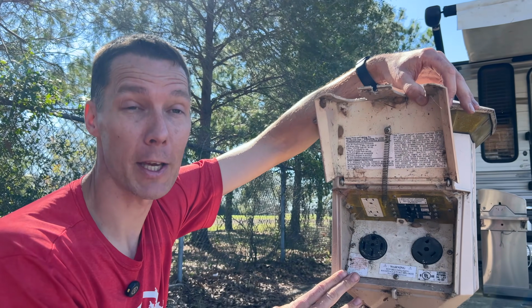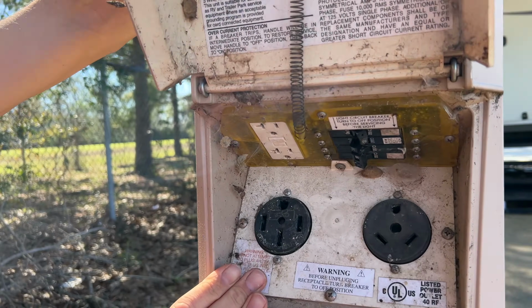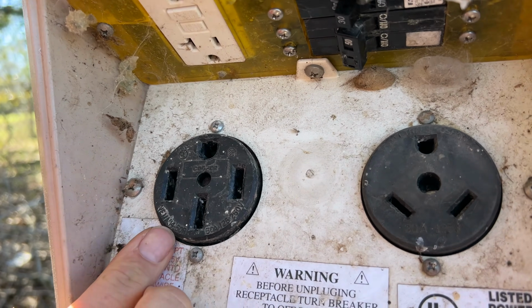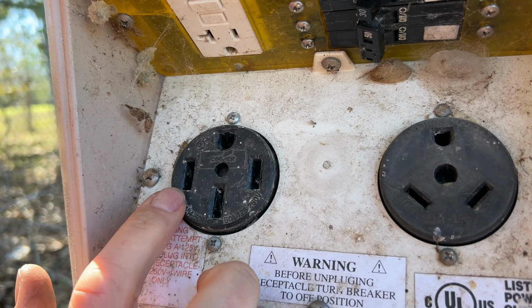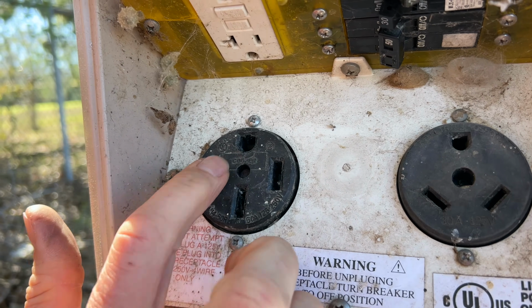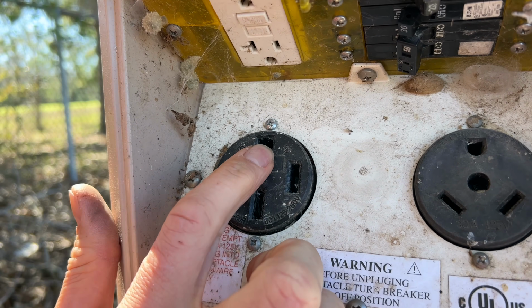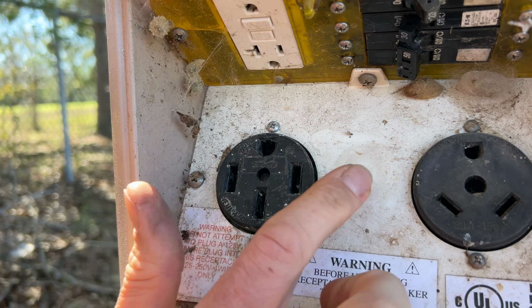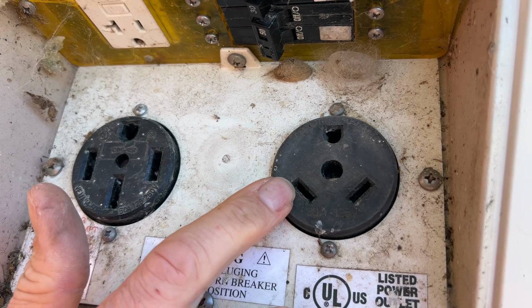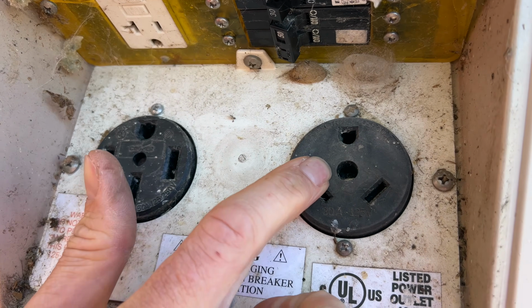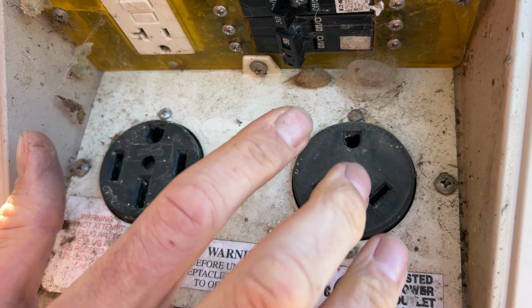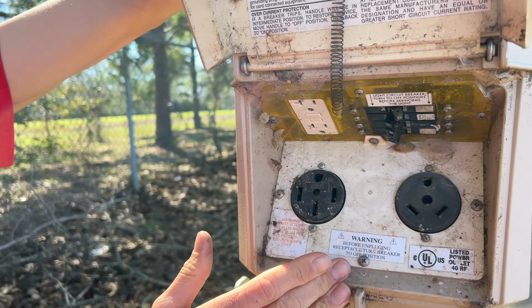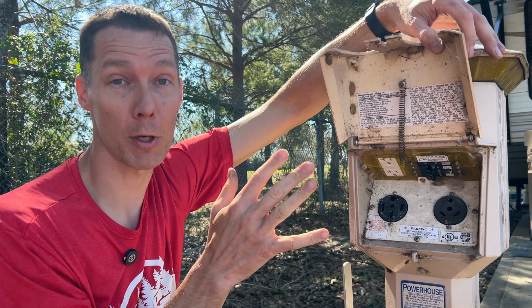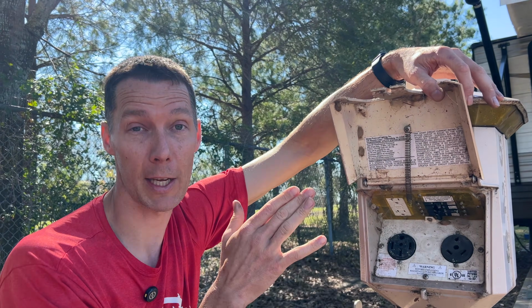And to answer a commonly asked question, how to test for an open ground: we're looking at the 50 amp side. If we read 0 volts between our hot and ground on either side, that means we have a bad ground connection inside of there. Just like on a 30 amp side, if between our hot and ground we read 0 volts, that means there's a bad ground connection somewhere behind this plug and outlet. At that point, you want someone who can work on that to come out and take care of that outlet issue.